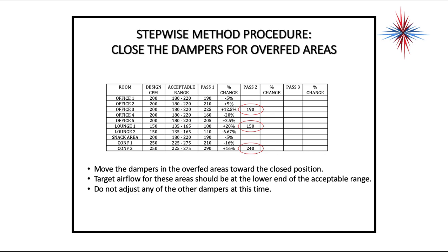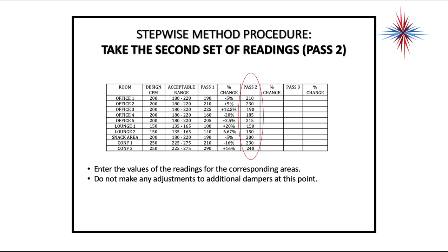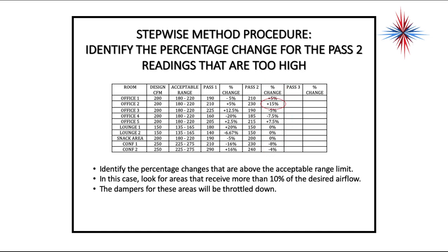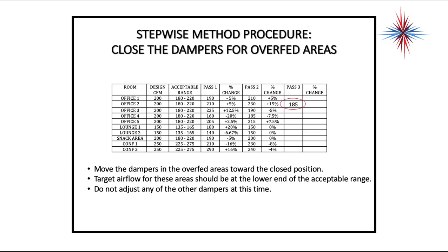Take a second set of readings — Pass 2. Enter the values for each area without making additional adjustments. Calculate the percentage of change again. Notice that a lot of things have started to line up. There's now one value still outside range: Office 2 is at 15%, outside my 10%. Throttle that damper down, targeting the lower end of the acceptable range. Leave everything else alone, because you really won't need to touch those.